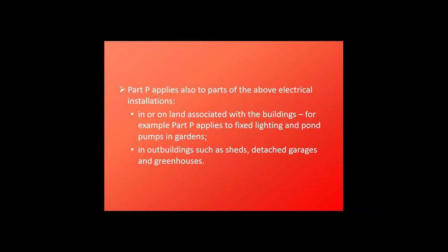Part P does apply to the land associated with the building, so potentially external lighting, pumps and the like, as well as supplies to things like sheds, garages, and greenhouses are all technically covered under the general scope of Part P of the building regulations. Although electrical work is covered under Part P, not all electrical work needs notification to a building control body, and a great deal of what we do in terms of electrics can be carried out without going through a formal process.